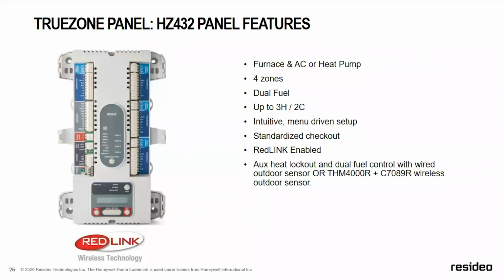This panel will also stage for you. If you have a standard thermostat and the homeowner likes it and you don't want to change it, but you put in a multi-stage furnace, you can run your staging by time or percentage of zones. Percentage of zones means if only one zone is calling, this panel will only stay in low stage. When more than one zone is calling, it will kick into high stage.